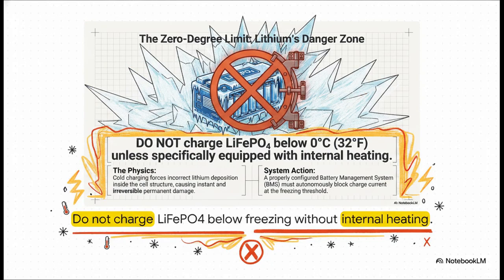And this brilliantly illustrates another terrifying physical reality for lithium, the 0-degree limit. Unlike lead acid, you absolutely, under no circumstances, can charge a LiFePO4 battery below freezing unless it has special internal heating. Doing that forces incorrect lithium deposition right inside the cell structure, causing instant, irreversible, permanent damage. A properly configured system just has to autonomously block cold charging entirely.